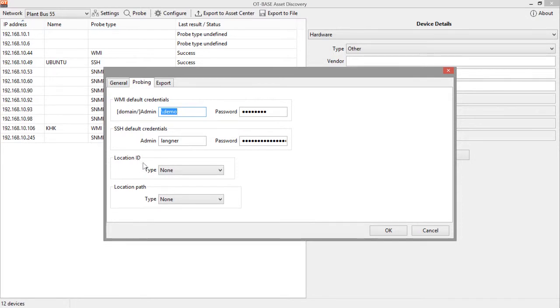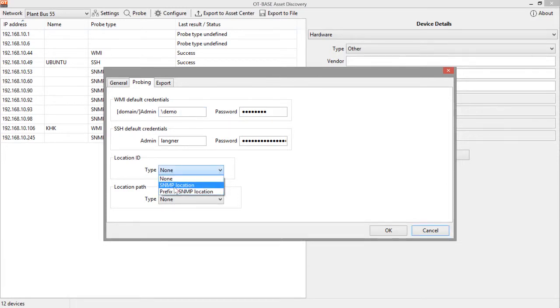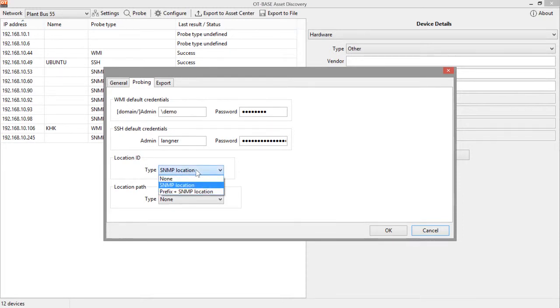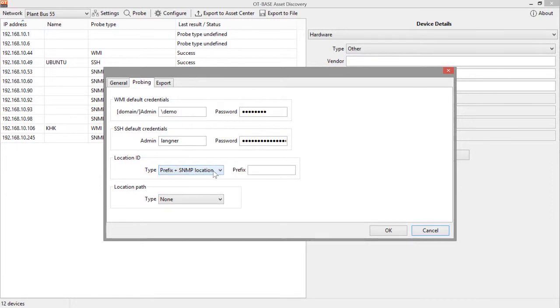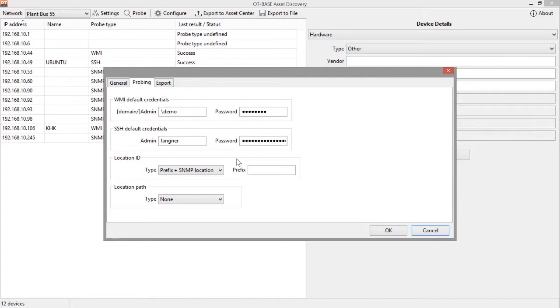The SNMP protocol allows you to set location information in the endpoints. First, if your location data is stored as an ID, then you have the option to just use the SNMP location that is set in the device or to provide a prefix to the SNMP location. So just as an example, if your location ID that is set via SNMP only identifies a specific cabinet, but you also want to indicate the room or the site name, the factory name of that cabinet, then you can add that as a prefix in this field.